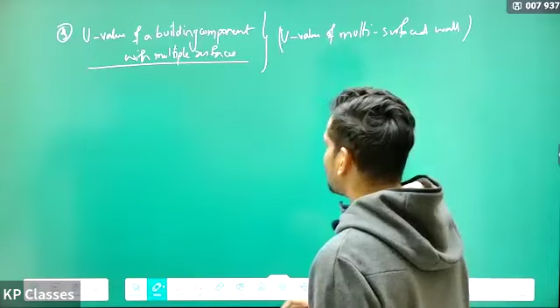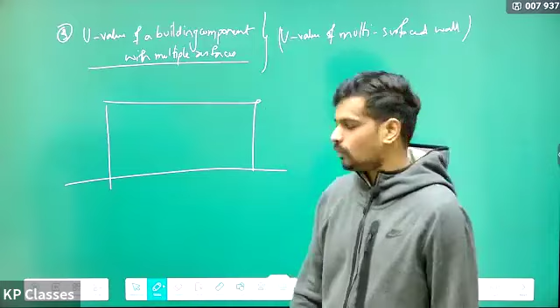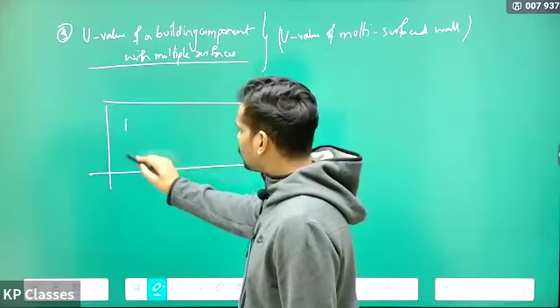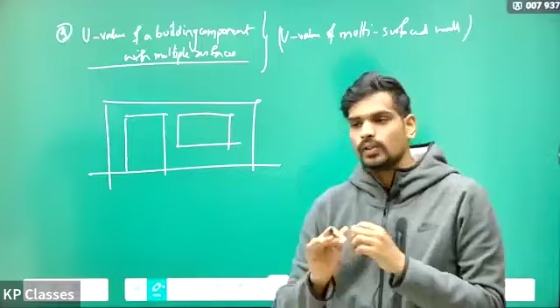So, U value of a multi-surface wall now. What is a multi-surface building component? Let us say this is a wall, for instance. It can have a door over here, a window over here. So these are multiple surfaces. These are not multiple layers. It's not like the window is behind the door, and the wall section behind the window. It's not that way. You don't have the door, then the window, then behind it the wall section. It's all on the same surface. You have a wall surface on which you have the door, and everything is in parallel on the same surface. In such cases, how do you calculate the U value of such a multi-surface wall?